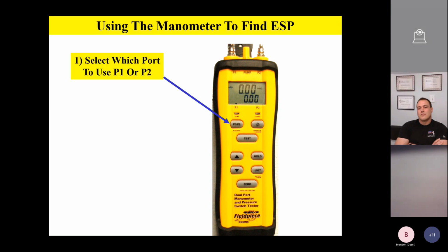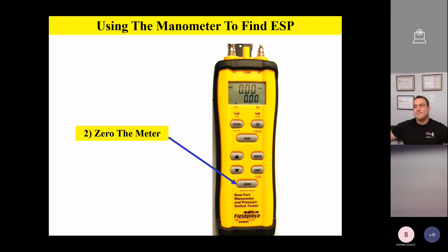So what we're going to do, we're going to select which port we're going to use, P1 or P2 on this particular tool. And so we have 2 ports. We've got P1 and P2 on this particular tool. So we're going to select which one we're going to use. This next thing we're going to do is, once we hook our hose up and our static pressure probe, we're going to go ahead and zero the meter. So you can see there's a place to zero the meter, so we get an accurate reading.